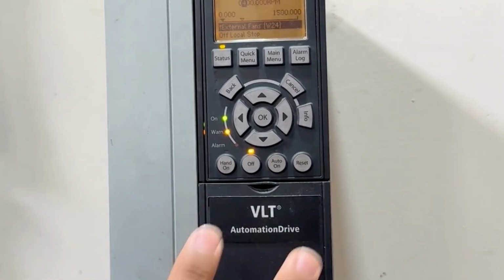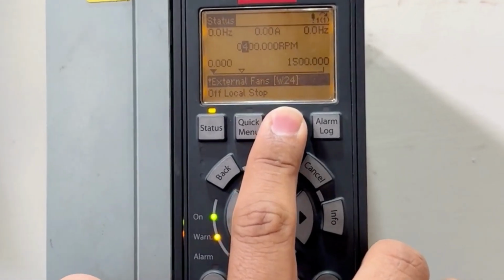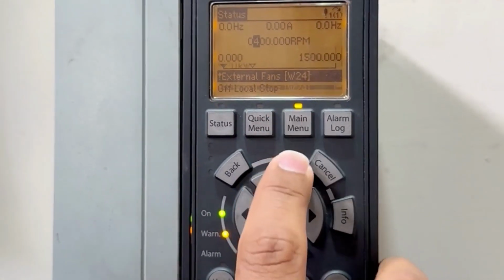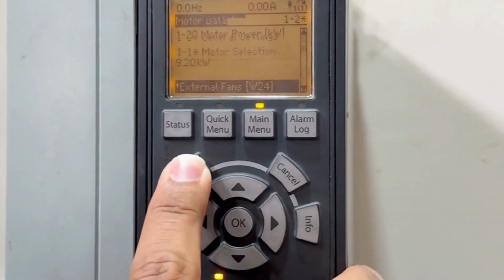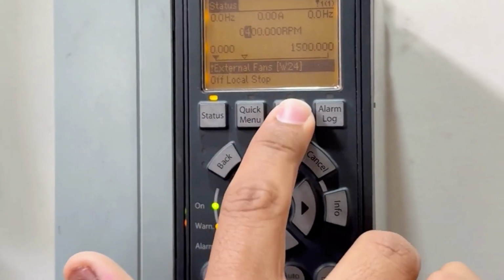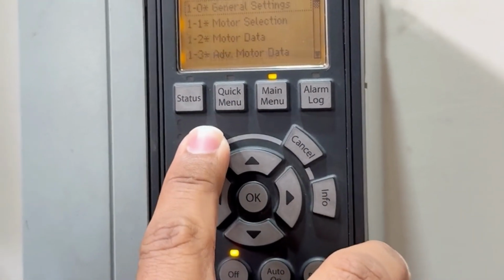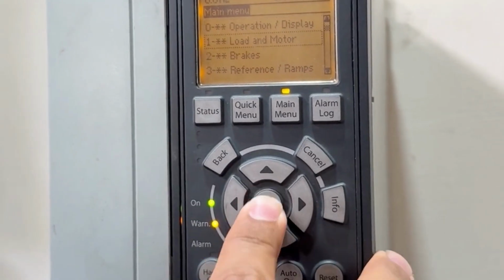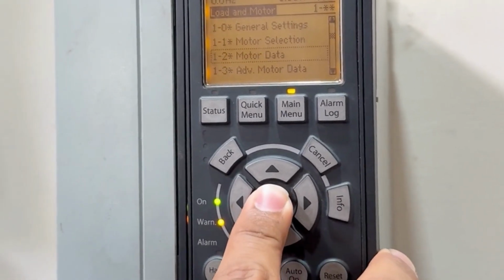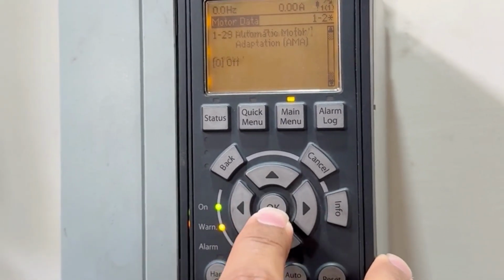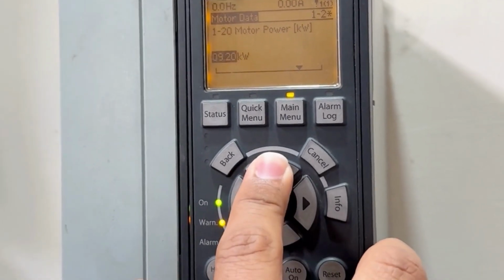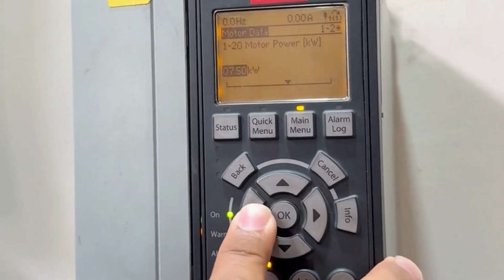Before running the motor, we first configure the motor parameters in the VFD according to the motor nameplate. First, we go to the main menu, then we select Load and Motor Settings. After that, we enter the motor data section.